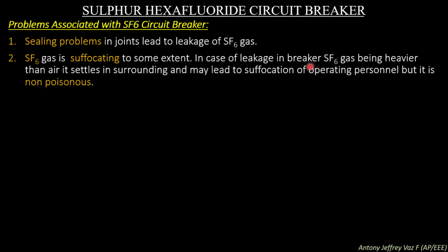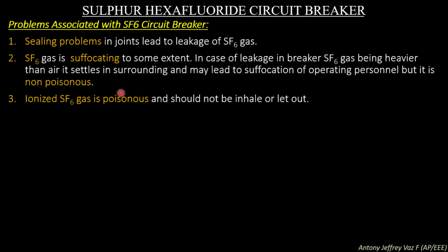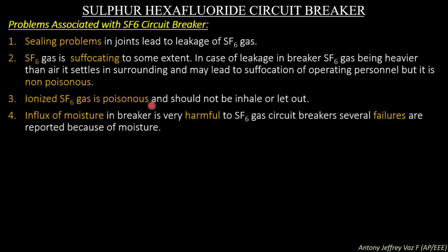SF6 gas is suffocating to some extent. In case of leakage in breakers, SF6 gas being heavier than air settles in the surroundings and may lead to suffocation of operating personnel, but it is non-poisonous. So SF6 gas is non-poisonous, but it will suffocate operating personnel who breathe it. Ionized SF6 gas is poisonous and should not be inhaled or let out.